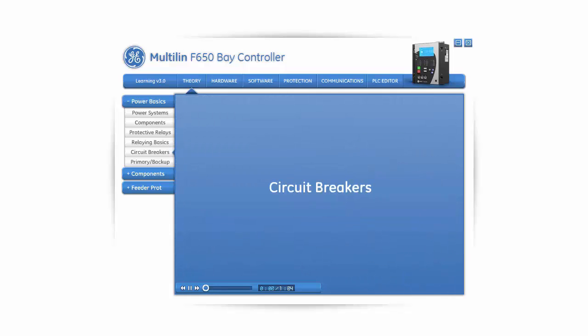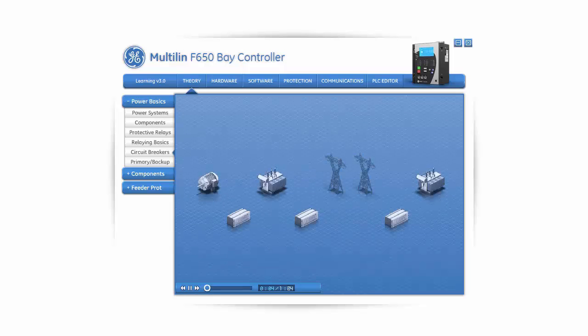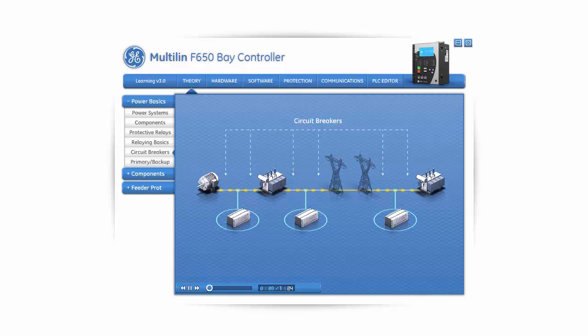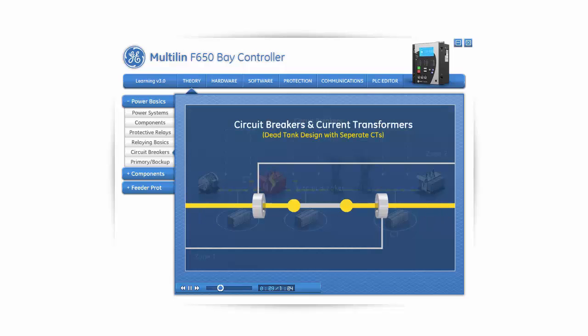Circuit breakers. Circuit breakers are an essential part of any protection scheme. At least one or more circuit breakers, in conjunction with the relaying equipment, are required to isolate a faulted power system component. A circuit breaker is defined as a mechanical switching device capable of making, carrying, and breaking currents under normal or abnormal circuit conditions such as those of a short circuit. CT placement with circuit breakers.